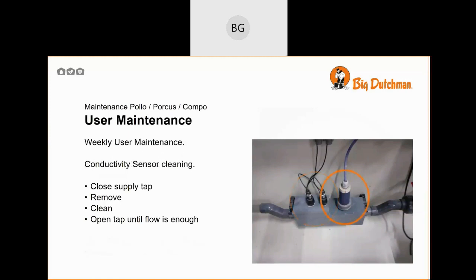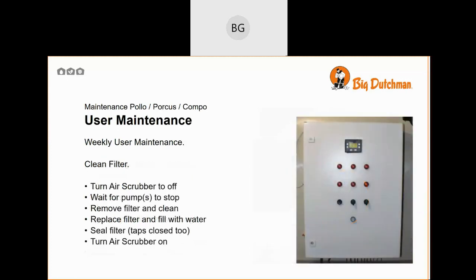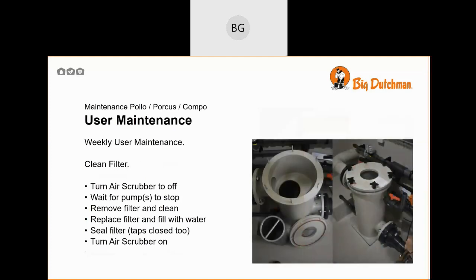Repeat this cleaning with the conductivity sensor. In the same way, close the tap, remove, clean, reinstall, and open the tap. Cleaning the filter is also a weekly user maintenance task. Turn off the air scrubber and wait for the pumps to stop. Remove the filter, clean, fill with clean water, reinstall and seal, closing the taps too, and turn the air scrubber back on.